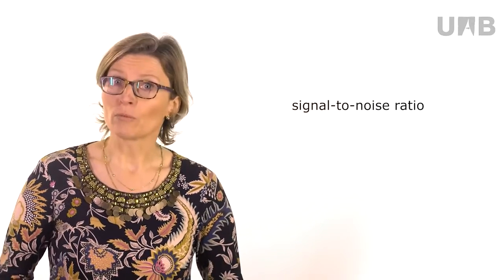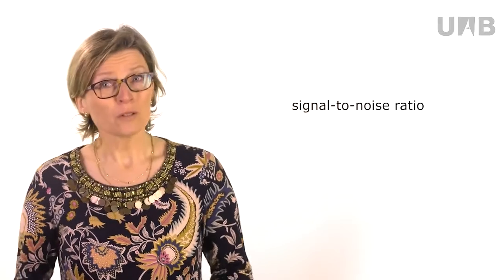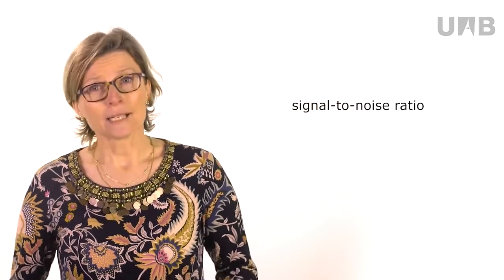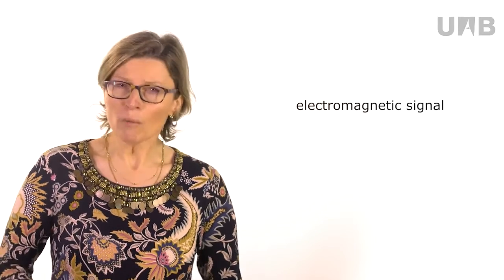The great advantage of the hearing loop is that it improves the so-called signal-to-noise ratio. More signal, that is more of the speaker's voice, less noise, that is less background noise. How does it work? Well, as the name says, a hearing loop or induction loop consists of a wire, the loop. The loop is connected to an amplifier to create a magnetic field. This electromagnetic signal is then picked up by the hearing aid or cochlear implant and more particularly by the telecoil that is built into the hearing aid or cochlear implant.